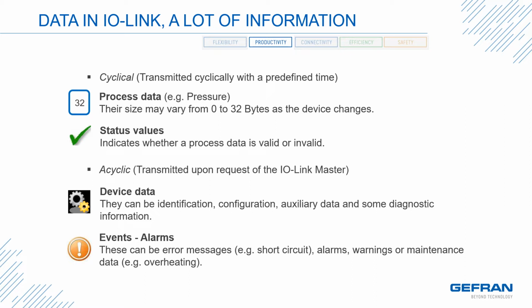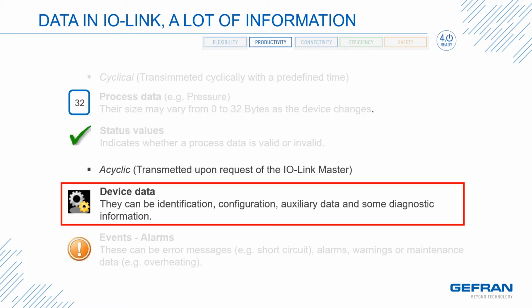Data is exchanged in an IO-Link network in two ways. The first is cyclical, which is transmitted at predefined times, such as process data, pressure for instance, as well as status values, whether data is valid or invalid. Then there's acyclic, which is only transmitted upon request from the IO-Link master, such as device data, which can be identification, configuration, auxiliary data, some diagnostic information, events, and alarms. On the next slide, we'll take a look at some of the device data that can be transmitted on the network.